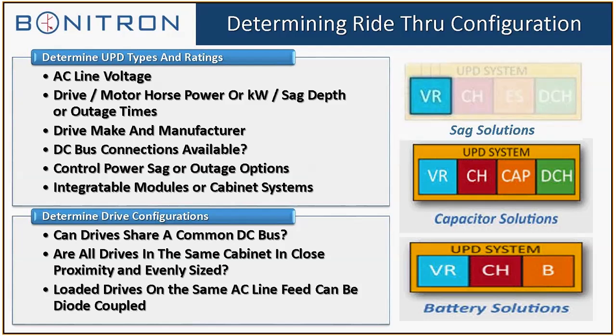We also would like to know, this is not as critical as some of the other parameters we need, the drive make and manufacturer. That's just sort of a sanity check. All the guys that specify ride-through here have an idea of what the drives can do, and whether there are any parameters that may bump heads with the ride-through function. Like I said, that's very rare. We've only come up with a couple of instances where there were drive parameters that caused an issue. But for the most part, with a standard drive, the ride-through will work just fine. You don't have to do anything to the drive. You don't have to configure it in any way, and it should work properly.